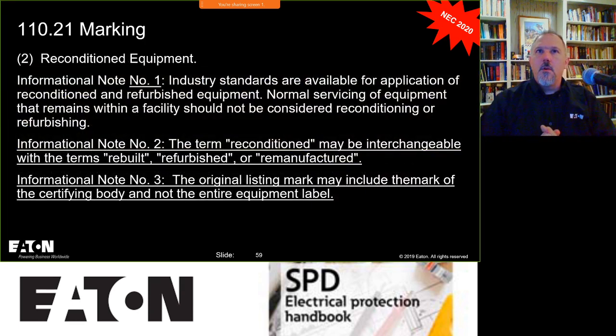So you have an exception for your industrials - reconditioned equipment, and they have a couple informational notes. The term reconditioned may be interchangeable with another term - remember in the definition we saw informational note number 2, and they moved that also over in 110.21. They're hammering a point home. It doesn't have to be in both locations, but it's good that it is - raises the awareness. And they tell you that the original listing mark may include the mark of the certifying body and not the entire equipment label.